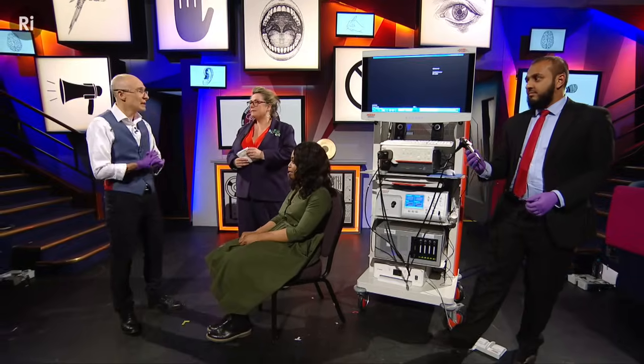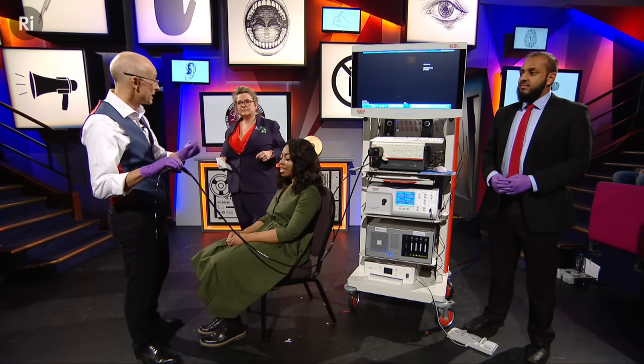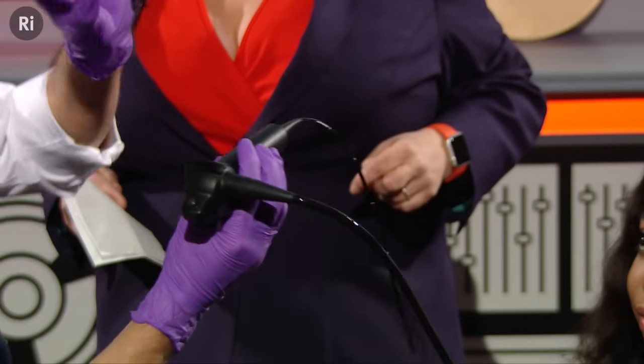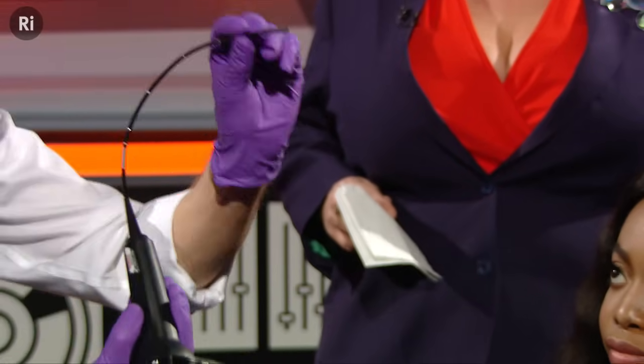This is equipment used in the clinic and hospitals every day — it's a nose endoscope stack used for looking at the throat and diagnosing people. It has three parts: a light source, a processor, and a strobe light generator. The endoscope itself used to use fiber optics, giving an insect-eye image, but now it has very high definition cameras on the end.